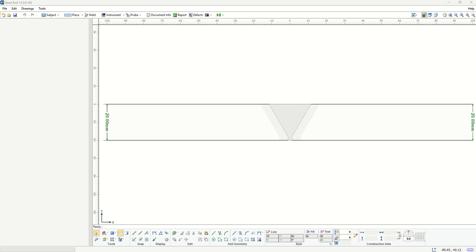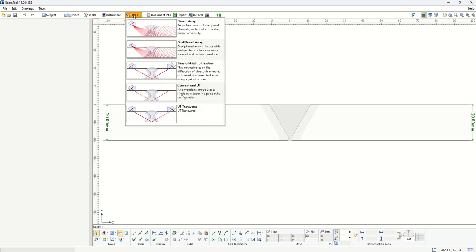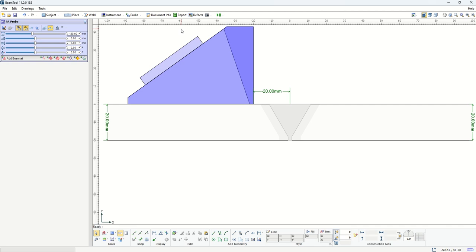With the current example of the flat piece with a single V, if you want to start with the phase array option under the probe, we can select phase array from the list of options for different UT techniques.